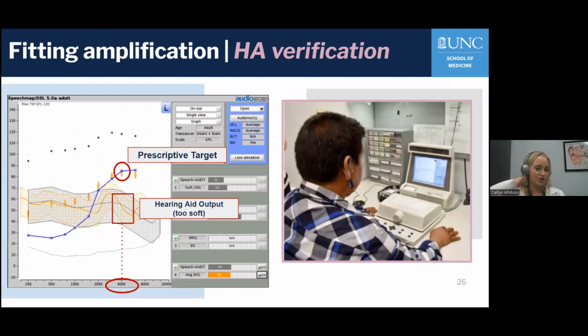This is a screenshot of a patient going through a hearing aid verification. This is the procedure called real ear measures. He has a hearing aid on the ear with the sound going in, and then there's a little microphone tube inserted in the ear to take a measurement of the sound. That measurement is being recorded and displayed on that screen so that I can see exactly how much sound he's hearing from each frequency.